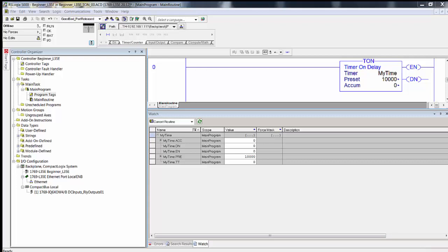The accuracy depended on the span or the maximum delay. So if you had a maximum delay of 1 second, then you could probably set it fairly accurately to tenths of a second. If the total possible delay was 10 seconds, then you could probably set it fairly accurately to single second units.